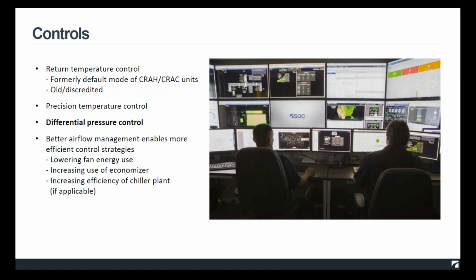And what we found is when customers install more equipment and turn it on, our fans automatically adjust to compensate, to maintain that set point. So they'll speed up slightly to maintain that set point. And similarly, if someone takes a piece of equipment out, our fans will match the airflow required by the servers. Next slide, please.